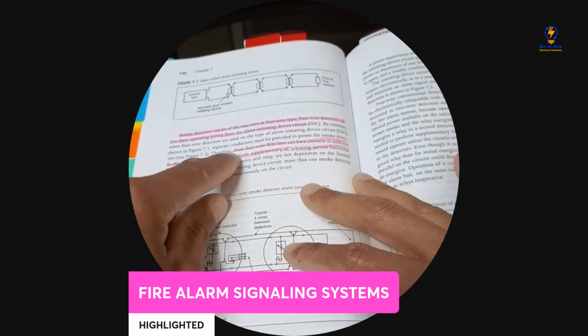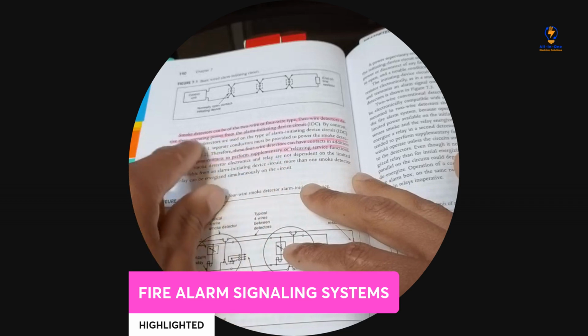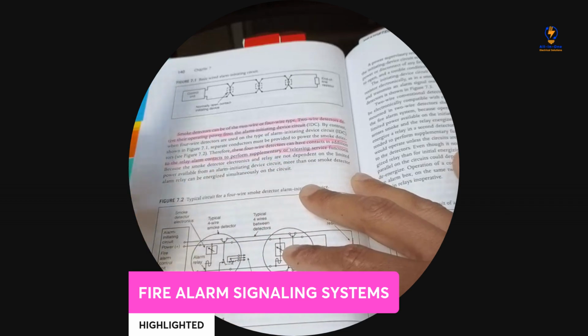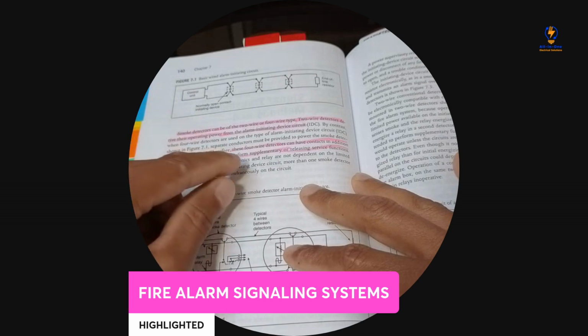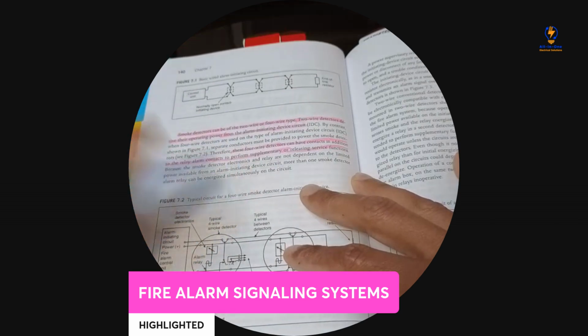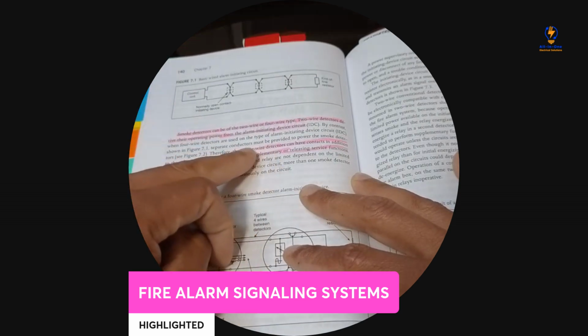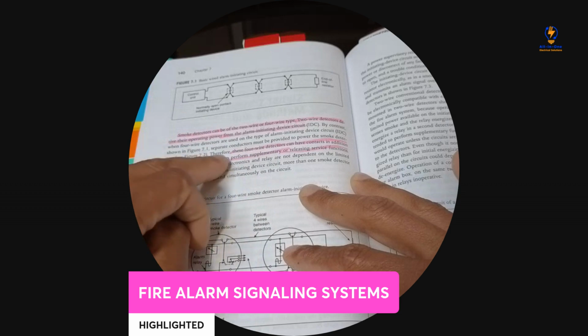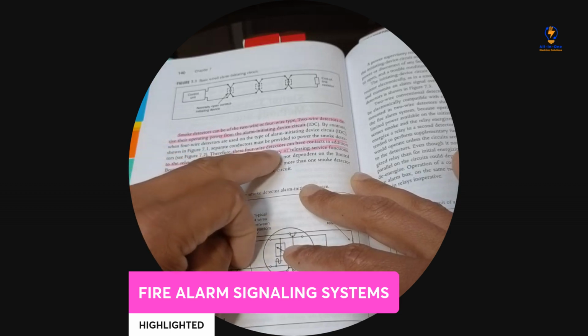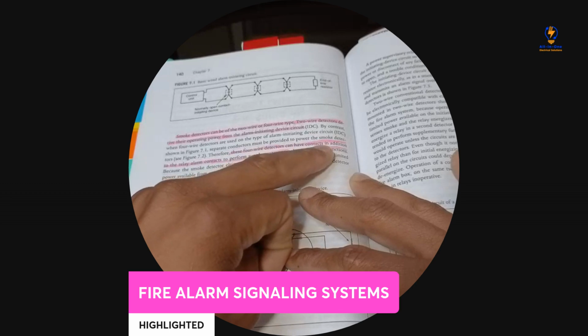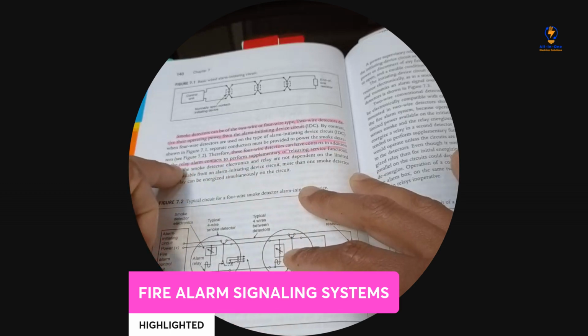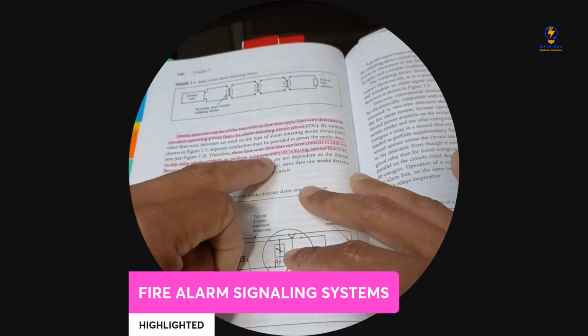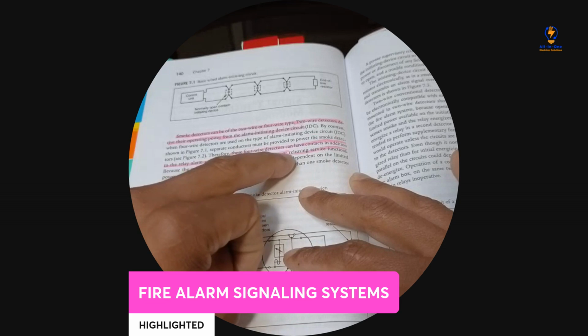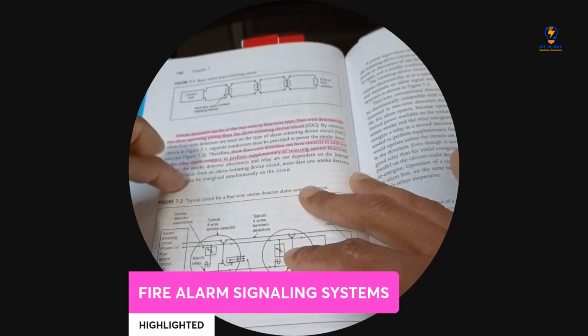And then as you see, moving all the way down, there's two ways that it can be wired. There's a 2-wire and a 4-wire, and the 4-wire right here. So if you're going along, therefore these 4-wire detectors can be connected in addition to the relay alarm to perform supplementary or releasing service functions. Highlight that.